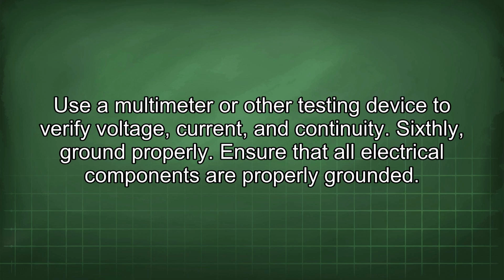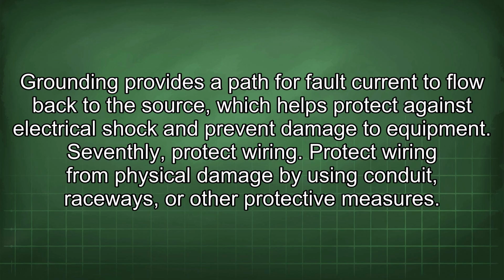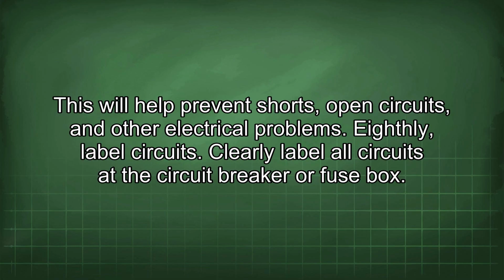Sixthly, ground properly. Ensure that all electrical components are properly grounded. Grounding provides a path for fault current to flow back to the source, which helps protect against electrical shock and prevent damage to equipment. Seventhly, protect wiring. Protect wiring from physical damage by using conduit, raceways, or other protective measures. This will help prevent shorts, open circuits, and other electrical problems.